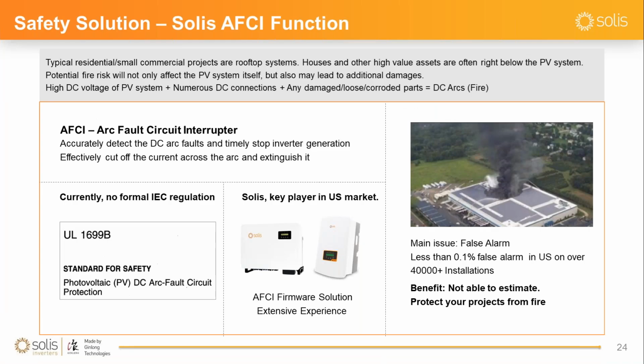And then back to the AFCI function, AFCI protection. Typically, residential or small commercial projects are rooftop systems, so they are built on top of the building, and there are a lot of houses or other high value assets under the PV system. And because the system normally has a quite high DC voltage, and there are a lot of DC connectors between the solar modules, you need to use MC4 connectors to link them.